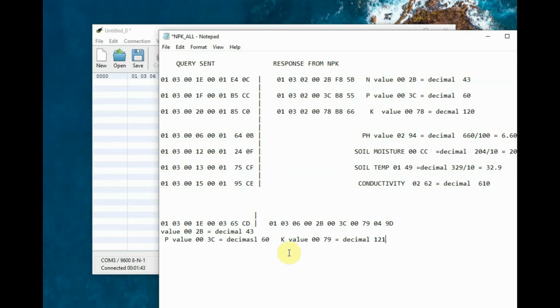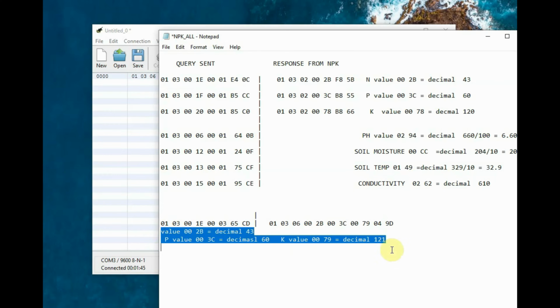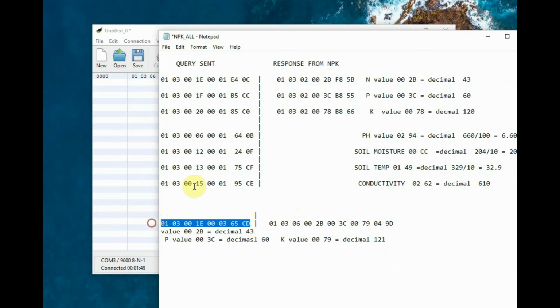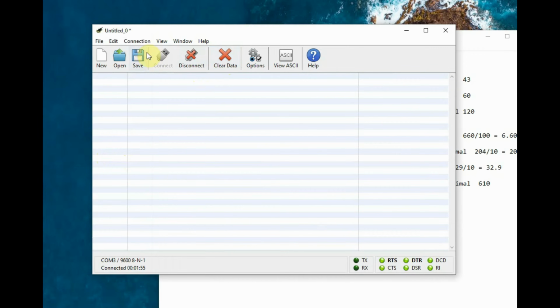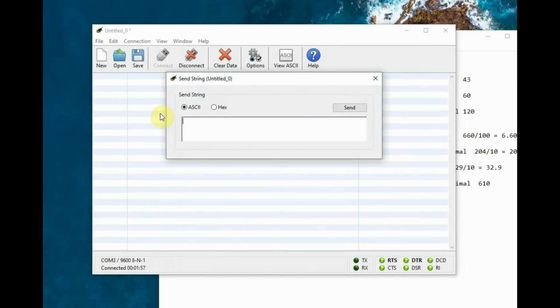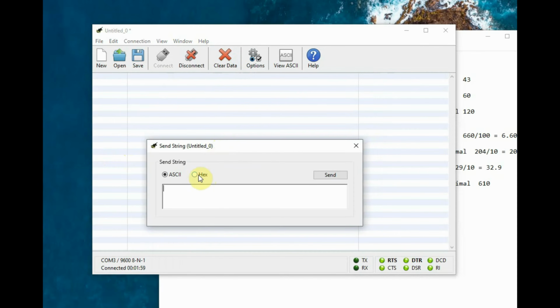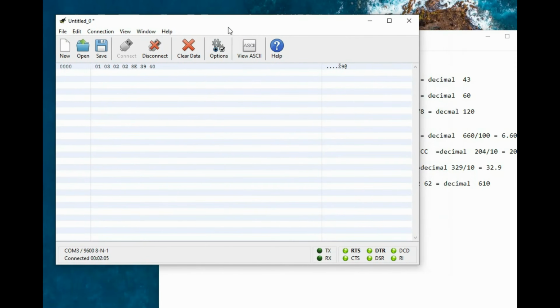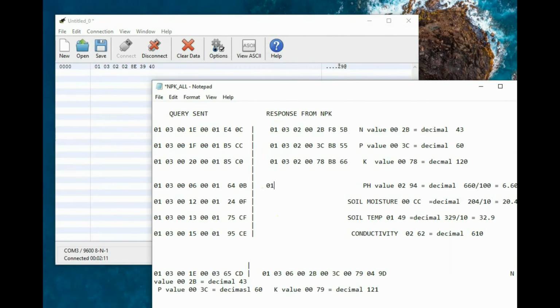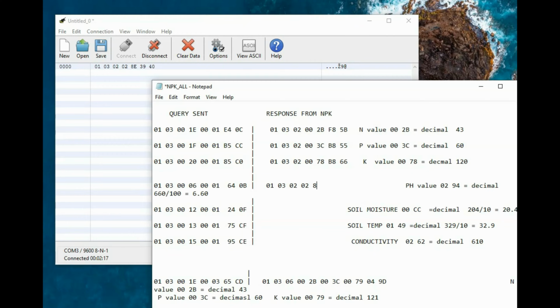So here, instead of sending NPK as 3 separate arrays, we are sending a single array to read the data from the 001E starting address. In the same way for pH value, we send 01, 03, 00, 06. 06 is the address, and then 0001, that is 1 byte of data, and paste it under the send string to get the value. Paste the received data into the notepad.